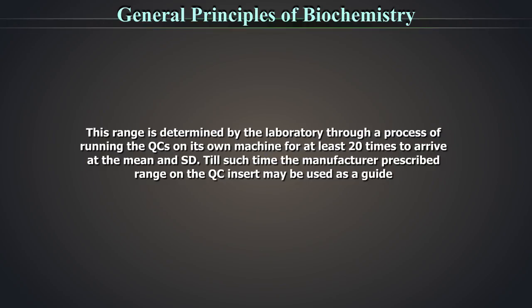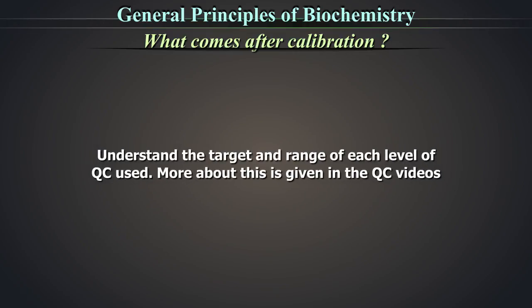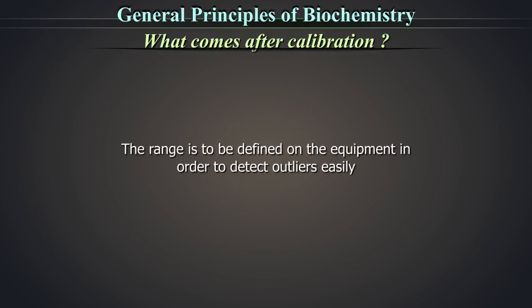Till such time, the manufacturer prescribed range on the quality control insert may be used as a guide. Understand the target and range of each level of QC used. More about this is given in the QC videos. This range is to be defined on the equipment in order to detect outliers easily. Reconstitution of QCs are explained in the QC module.